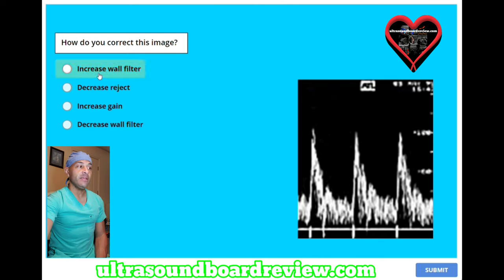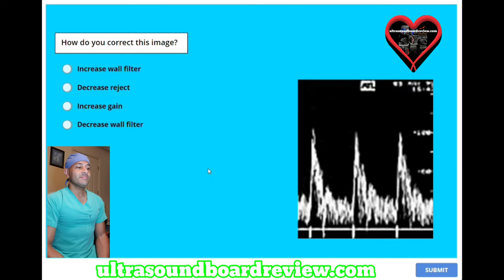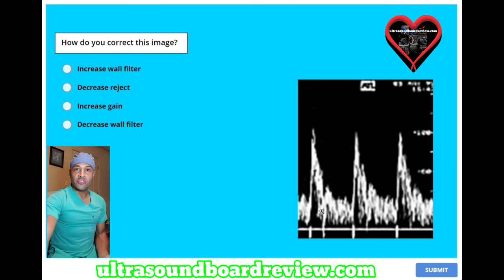How do you correct this image? A, increase wall filter. B, decrease reject. C, increase gain. Or D, decrease wall filter. This image shows three little wall thump artifacts, which means your wall filter is turned down too low. So what you want to do is increase your wall filter to eliminate it.